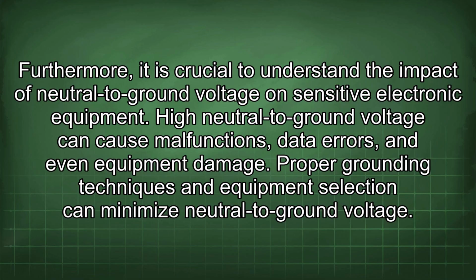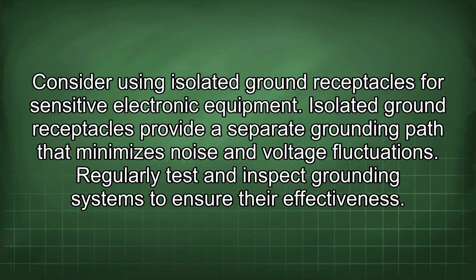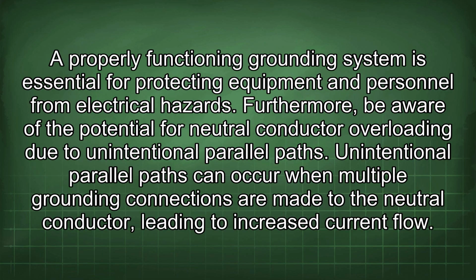Furthermore, it is crucial to understand the impact of neutral to ground voltage on sensitive electronic equipment. High neutral to ground voltage can cause malfunctions, data errors, and even equipment damage. Proper grounding techniques and equipment selection can minimize neutral to ground voltage. Consider using isolated ground receptacles for sensitive electronic equipment. Isolated ground receptacles provide a separate grounding path that minimizes noise and voltage fluctuations. Regularly test and inspect grounding systems to ensure their effectiveness. A properly functioning grounding system is essential for protecting equipment and personnel from electrical hazards.